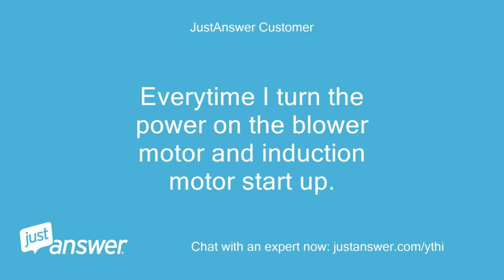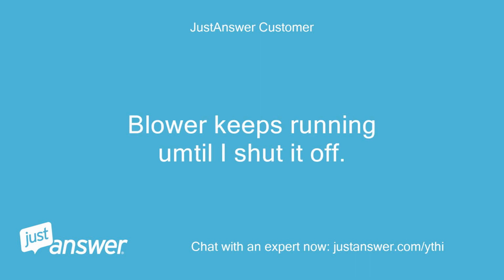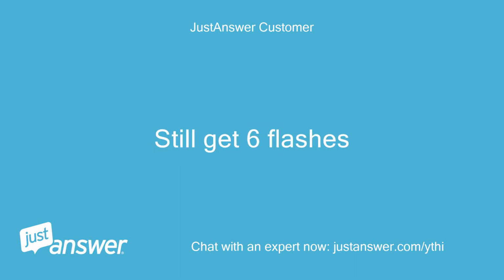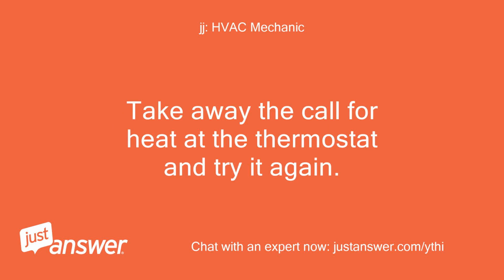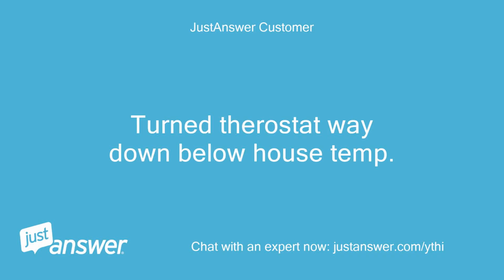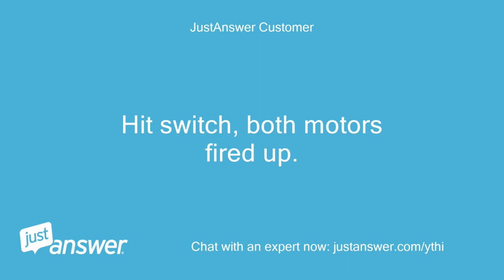Every time I turn the power on, the blower motor and induction motor start up. After 20 seconds, the induction motor stops. Blower keeps running until I shut it off. Still get 6 flashes. That's because you have a call for heat. Take away the call for heat at the thermostat and try it again. Turn thermostat way down below house temp. Pulled green wire on furnace. Hit switch, both motors fired up.